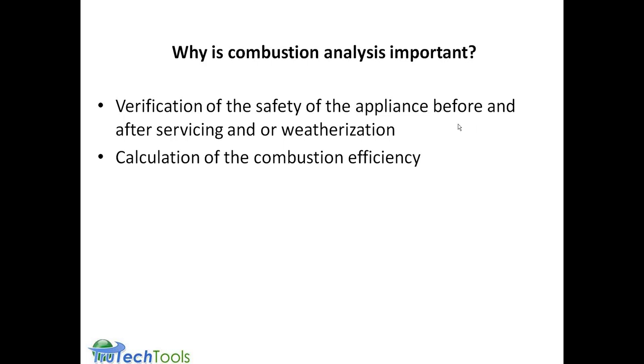The analyzers also calculate combustion efficiency in order to determine how efficiently the appliance is operating. And again, in the seminar tomorrow, we get into more about how the combustion efficiency is calculated and what the significance is. It's not AFUE. It's not thermal efficiency. It's a hybrid value. It points in the same direction as AFUE. Increasing AFUE equipment has higher combustion efficiency, but it's kind of a hybrid parameter.